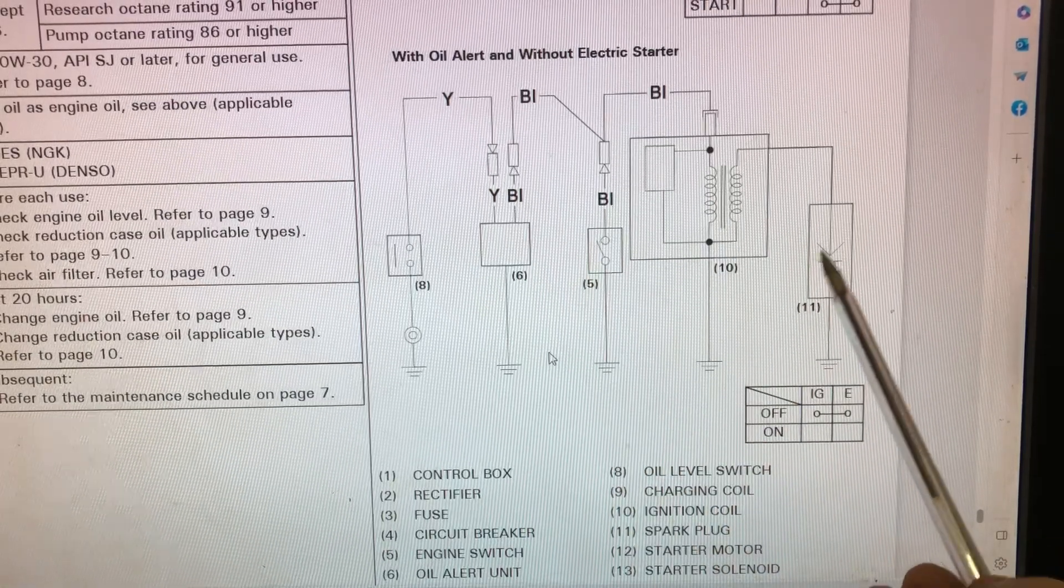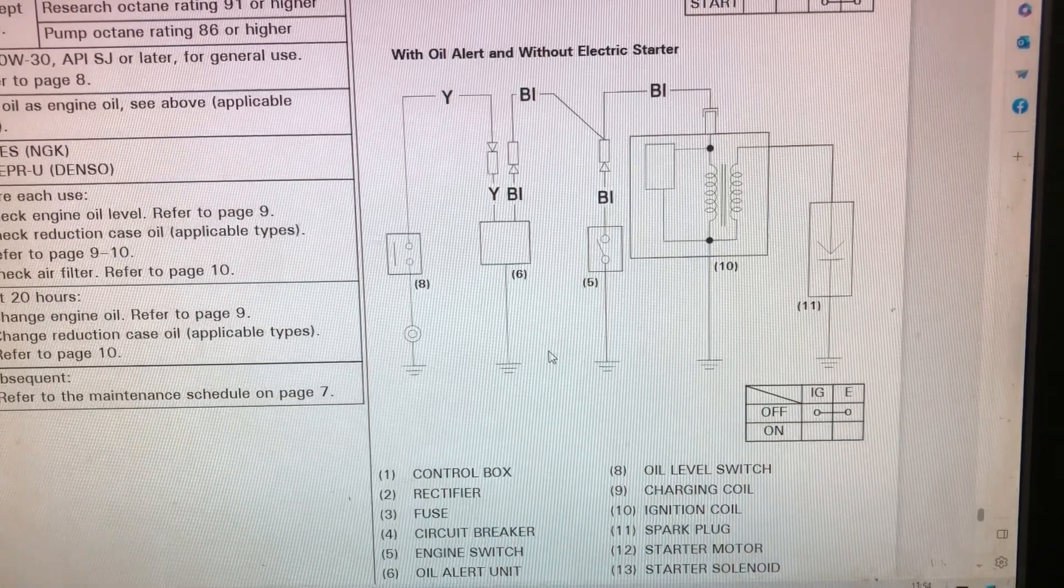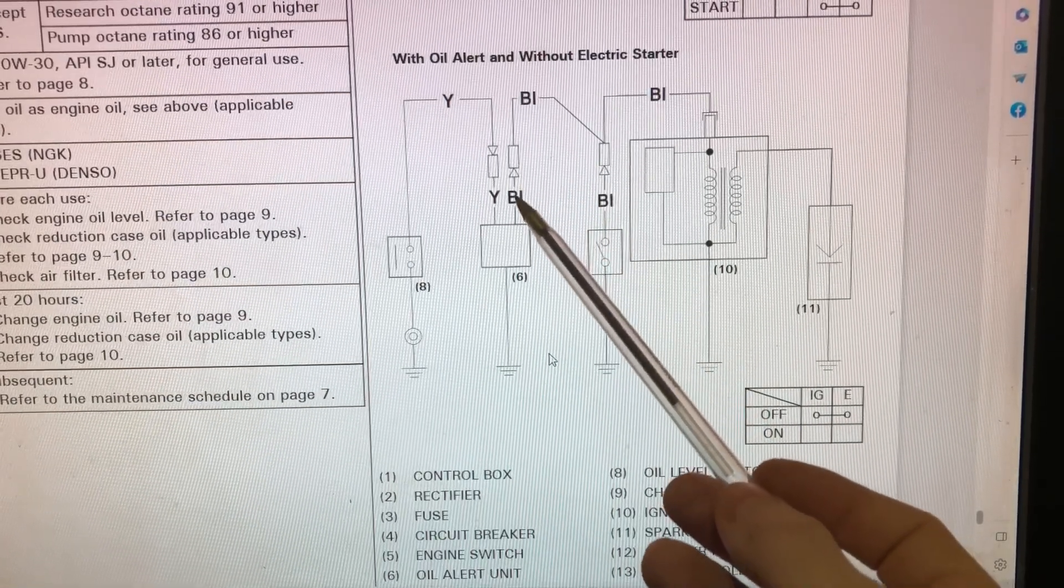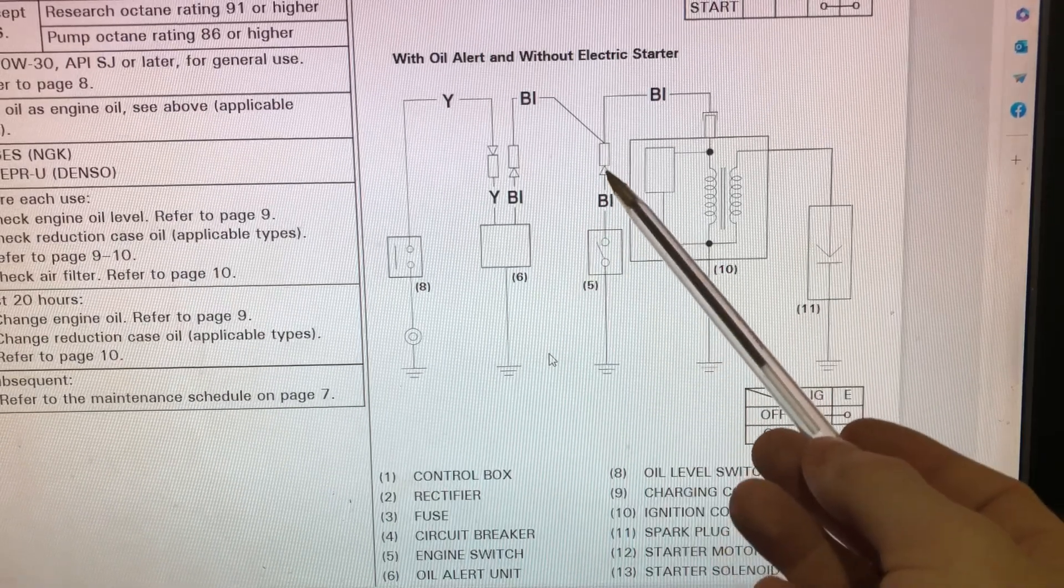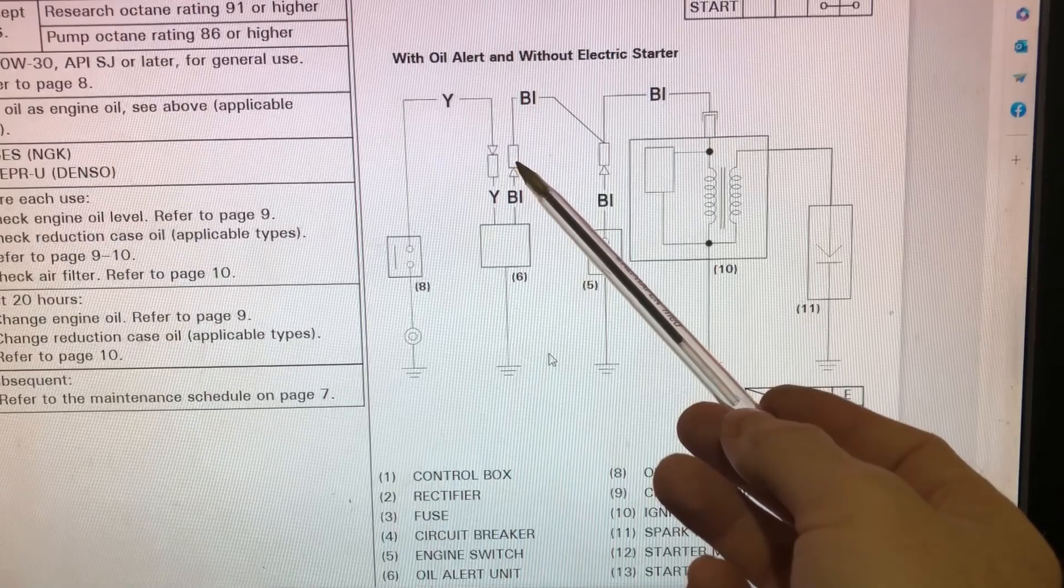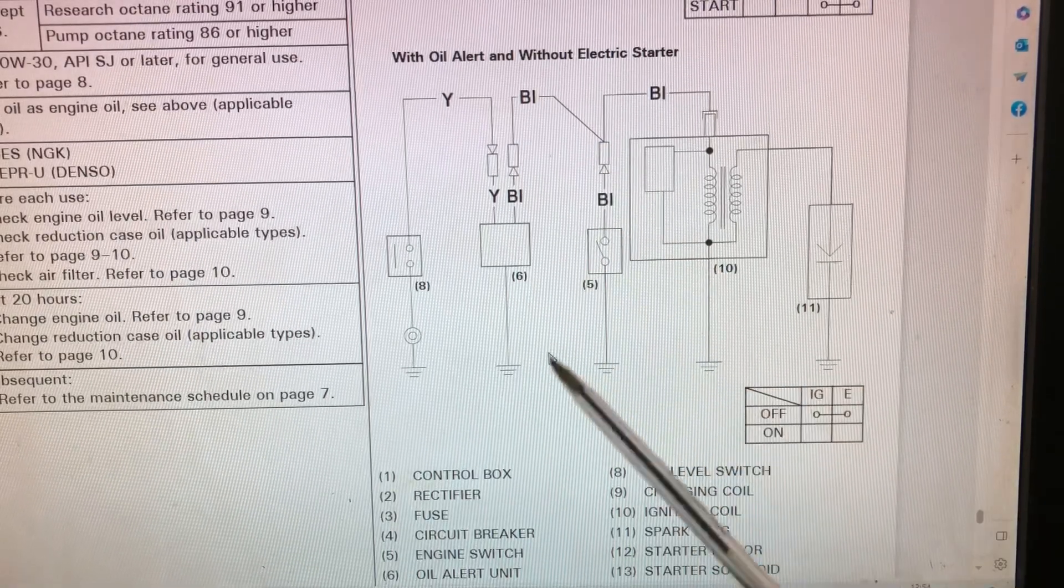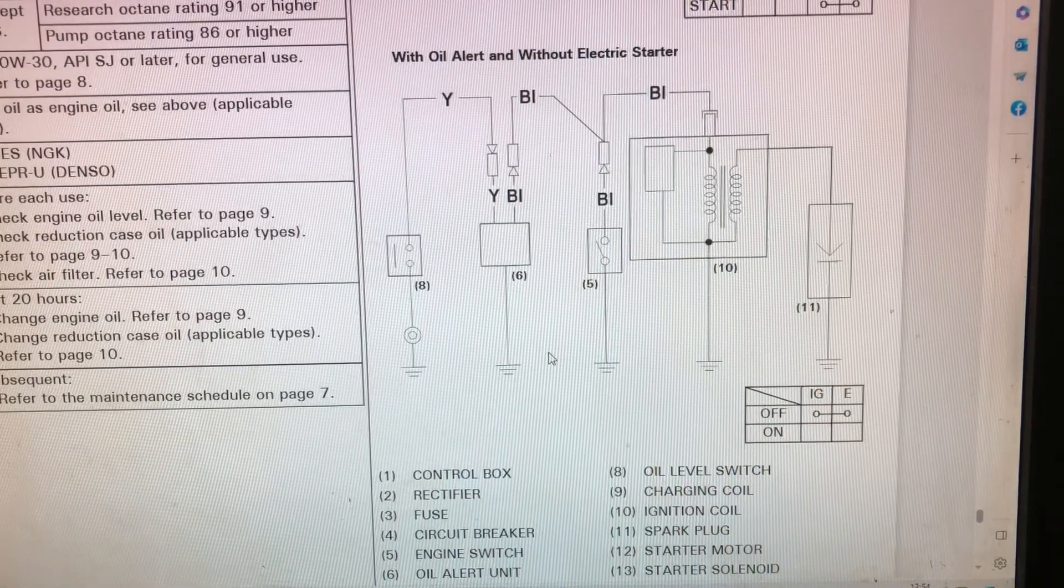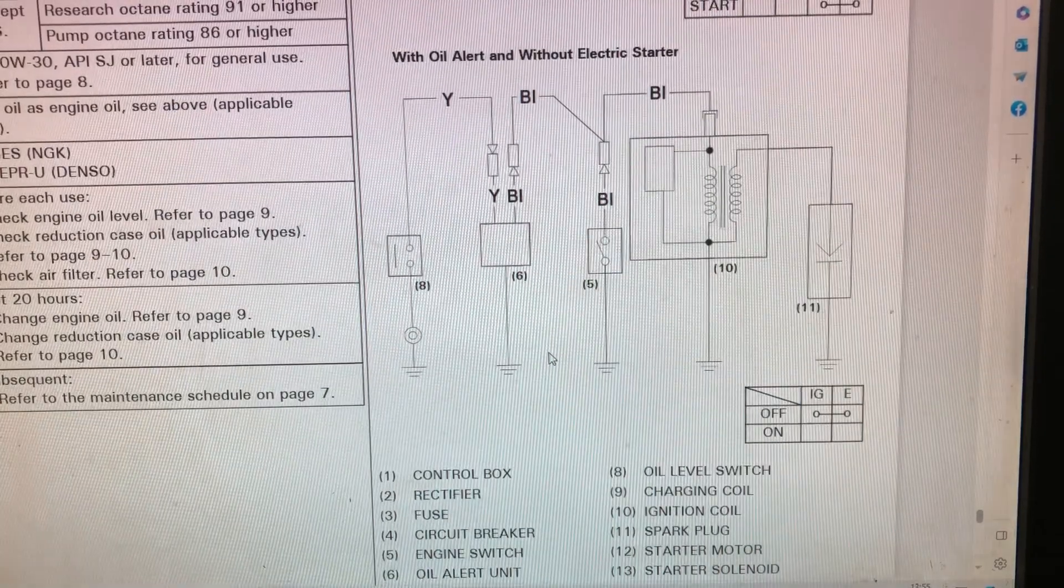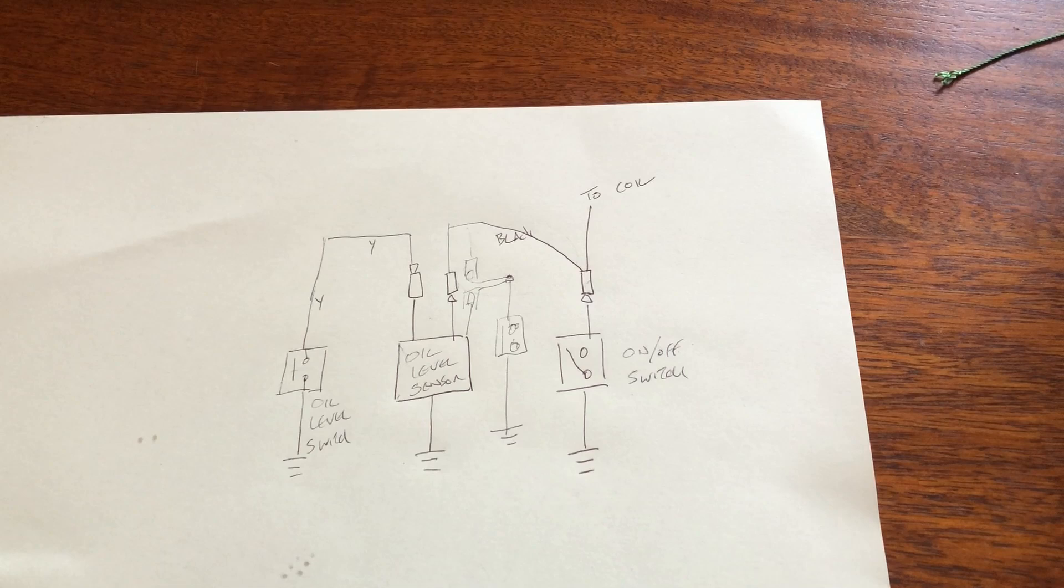Basically all you've got to do is somewhere in this circuit here, whether you do it at that connection or that connection, put an emergency stop between there and there and earth. This is simply done, but obviously you've got to choose the right emergency stop.